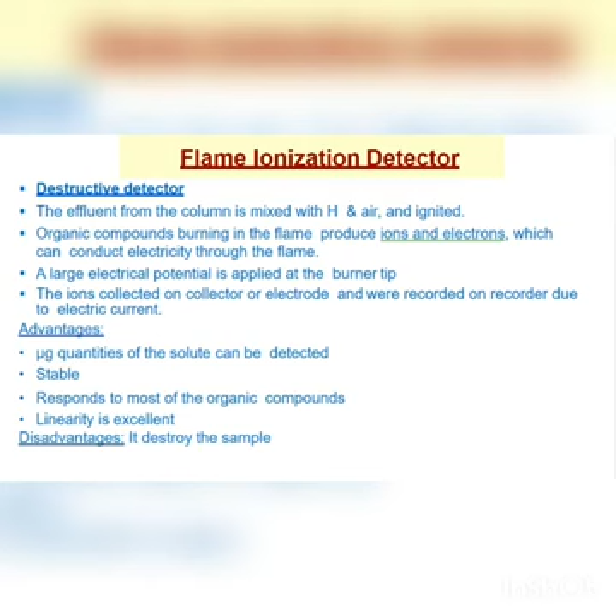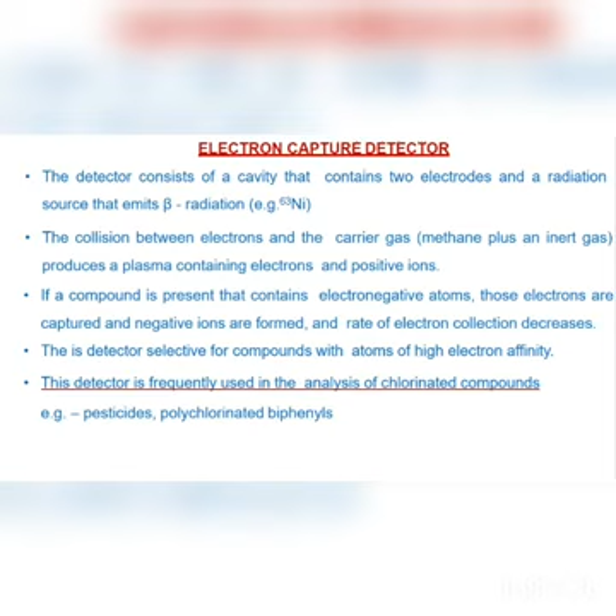Now, the third detector is the electron capture detector. Here, in the electron capture detector, a beta particle produced from a radioactive source interacts with the carrier gas. This beta particle ionizes the carrier gas and because of this a high current is produced. When a sample which has an attraction for electrons enters the detector, some electrons which are emitted from the carrier gas are captured by the compound. Therefore, a decrease in current is formed.